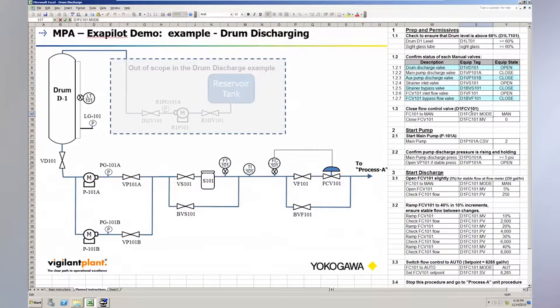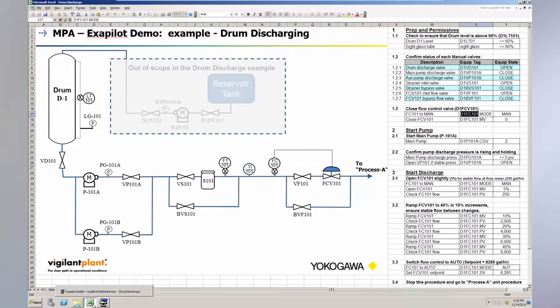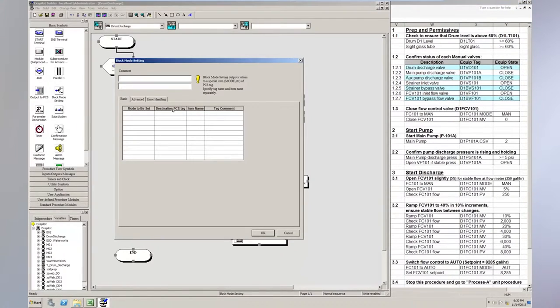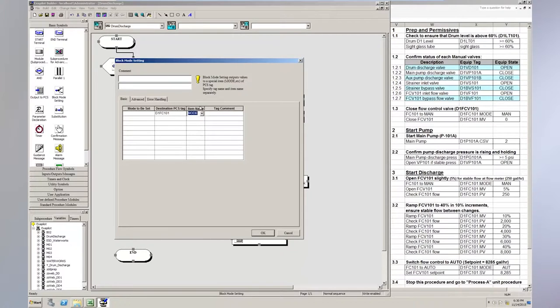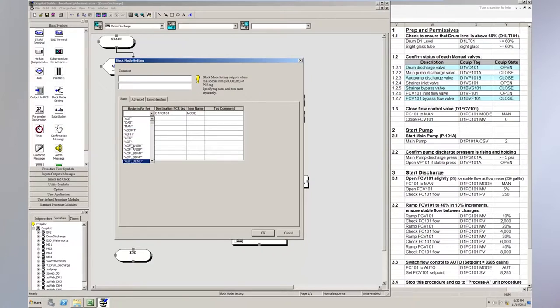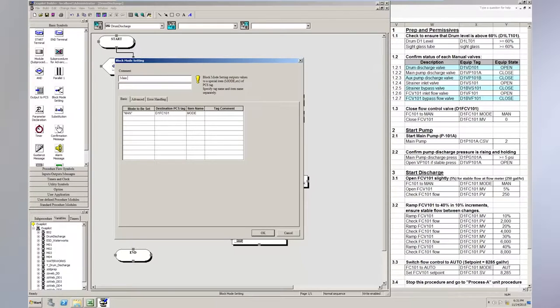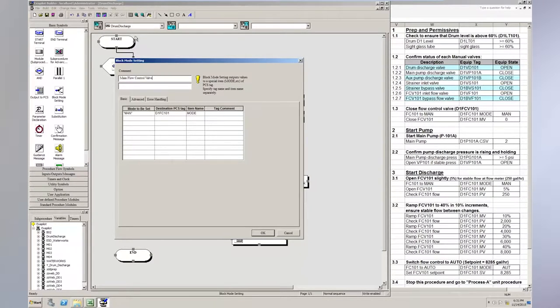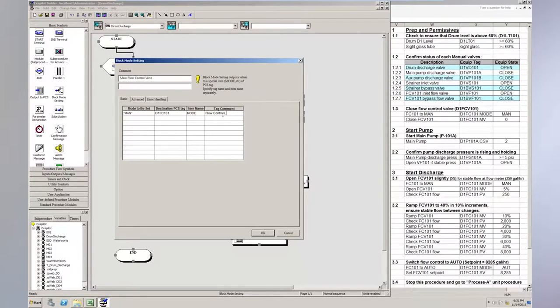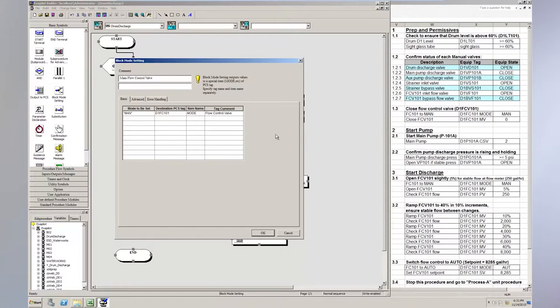So let's configure those. So we'll take the valve. Copy this tag name onto ExaPilot. So I can put this into my tag name segment. And then for the mode, for this mode block, it asks me for the parameter of the tag name separately from the tag name itself. So I need to use the drop down box and select mode. And then for the setting, it allows me to choose the enumeration. So I can choose manual. And I'll label this as main flow control valve. And this is the flow control valve.